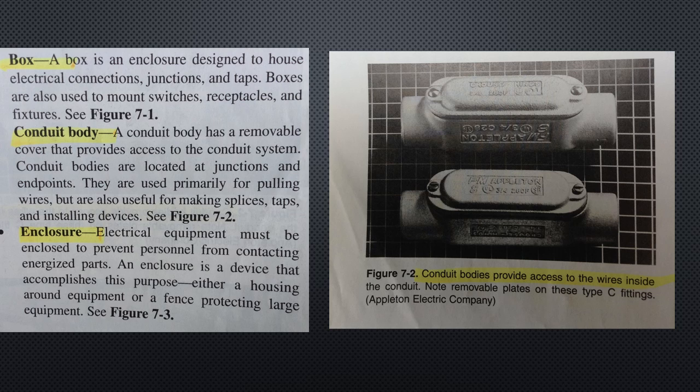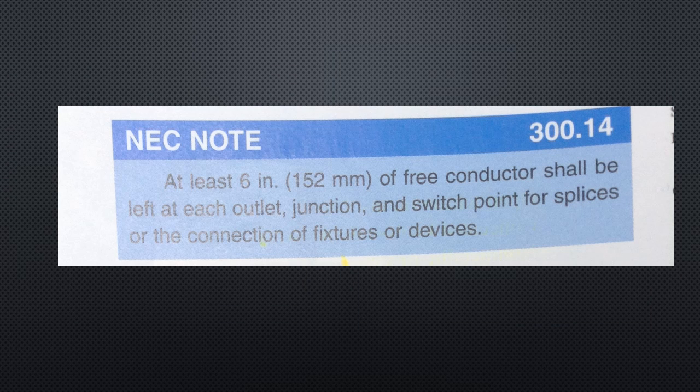NEC note: 300.14, at least 6 inches or 152 millimeters of free conductor shall be left at each outlet, junction, and also switch point for splices or the connection of fixtures or devices.